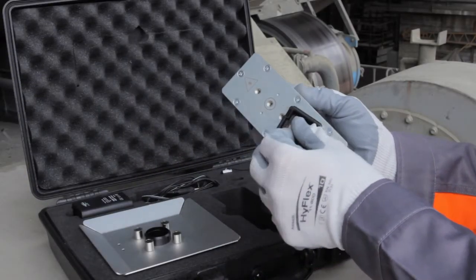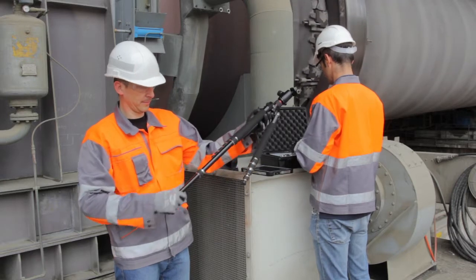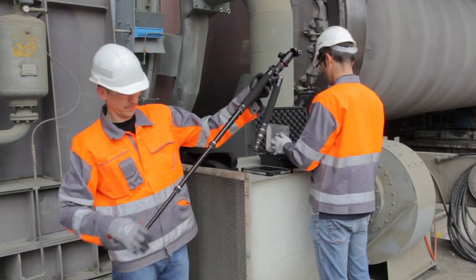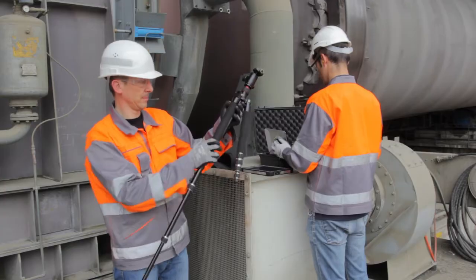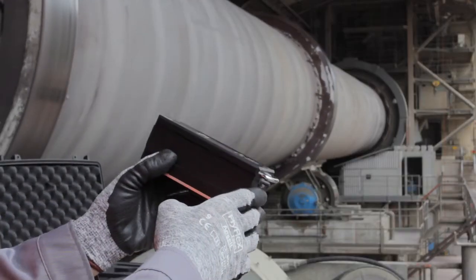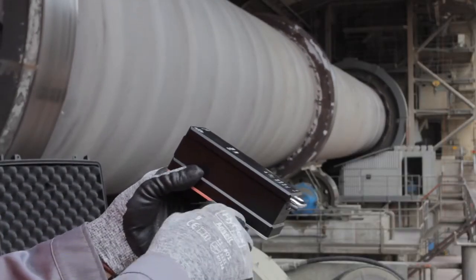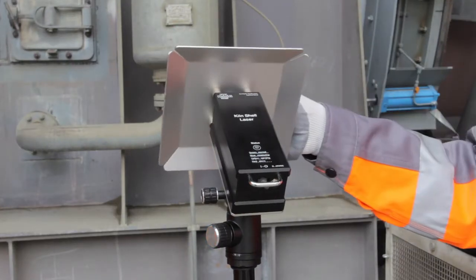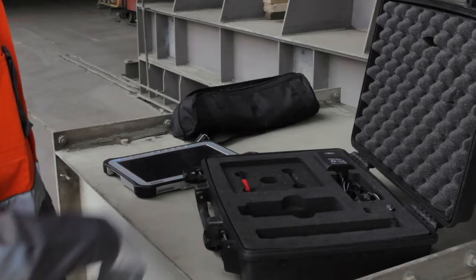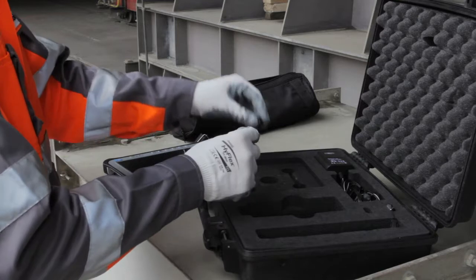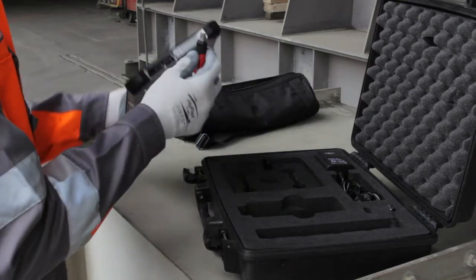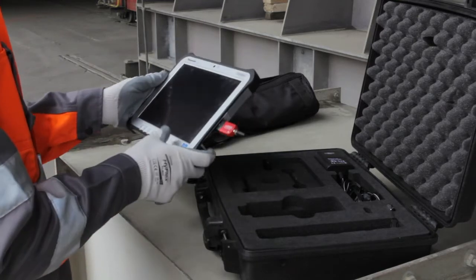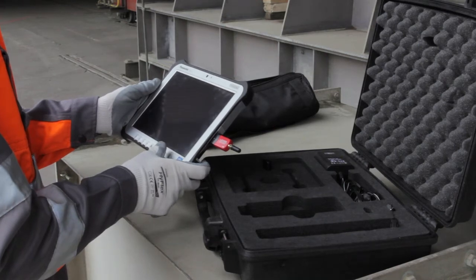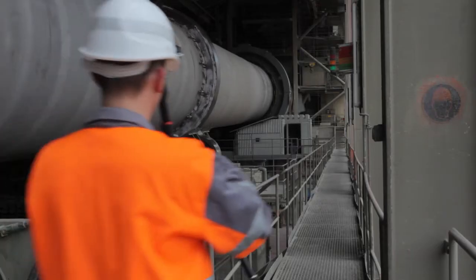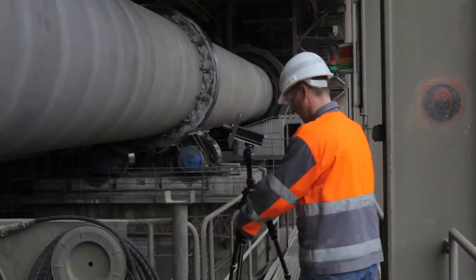The laser is typically mounted to the tripod, which comes with the toolkit. It can also be fixed with the clamp or on any other photo stand. The heat shield protects the laser from the heat radiation of the kiln. To connect the laser with the computer, the Bluetooth adapter has to be plugged into the laptop. Then start the software. When the tool is switched on, the green light appears.